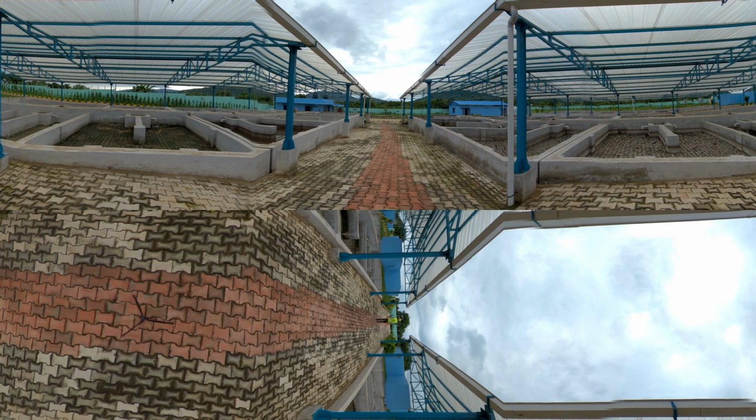The sand should be replaced every 3 years and the sand plus gravel should be replaced every 6 years. To do this, remove the coarse sand using a shovel and replace it. The new sand and gravel should be free from silt and clay. If it is not, then it should first be washed.